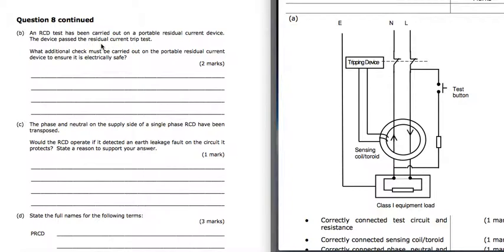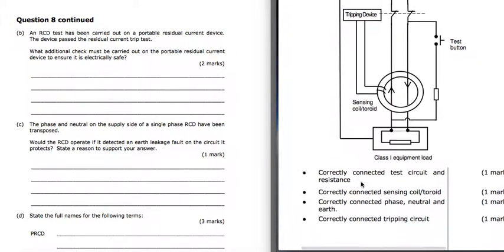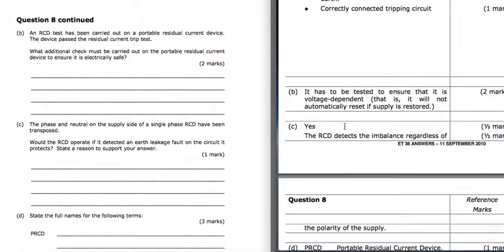The RCD test has been carried out on a portable RCD device. It's passed. What additional checks? Well, we want to make sure that when it goes off, it doesn't come back on when we restore the supply, so that it's voltage dependent. It won't automatically reset if we restore the supply.